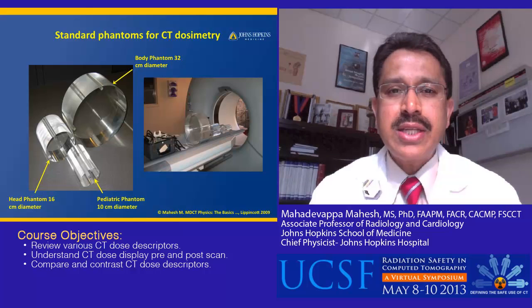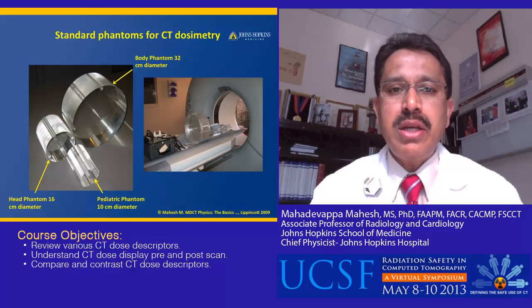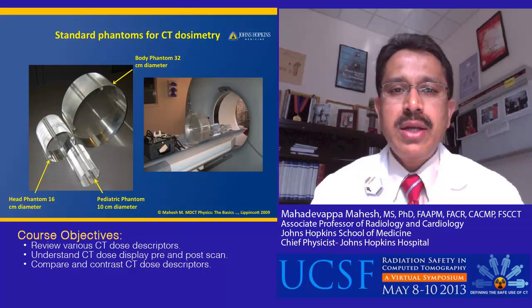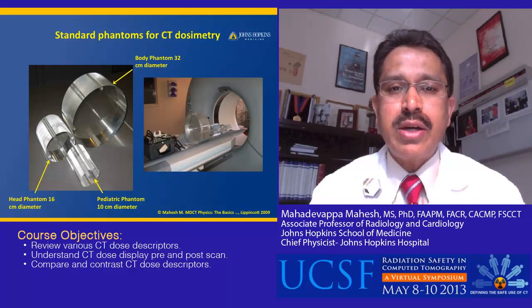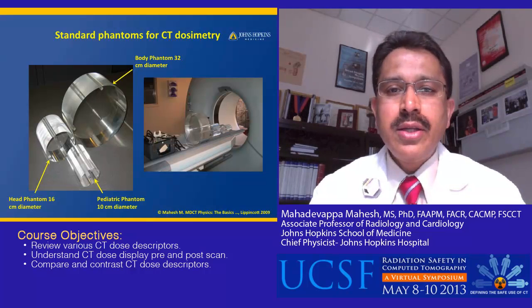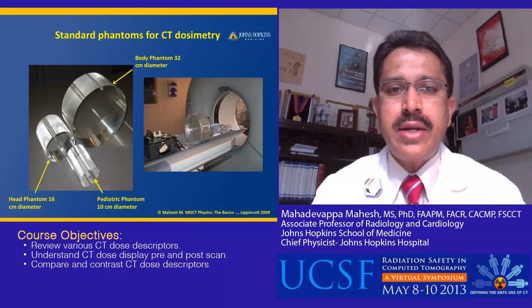Shown here are the standard CT phantoms used for CT dose measurement. The larger phantom, called the body phantom, is a 32-centimeter lucite cylinder with holes drilled in it, which are used to place the ion chamber — typically a 100-millimeter length chamber — inside during measurement. The second phantom is the 16-centimeter diameter head phantom. These two phantoms are historically used as the standardized CT phantoms for a lot of the measurements which are now available on CT scanners.